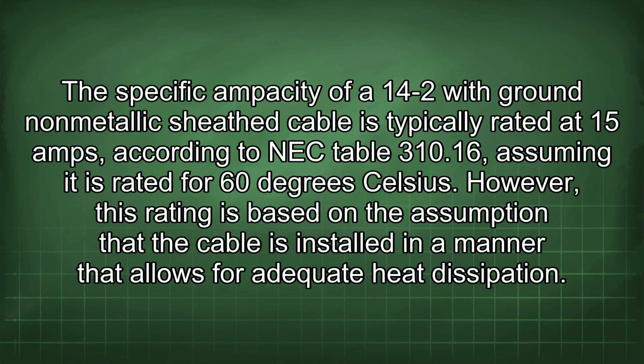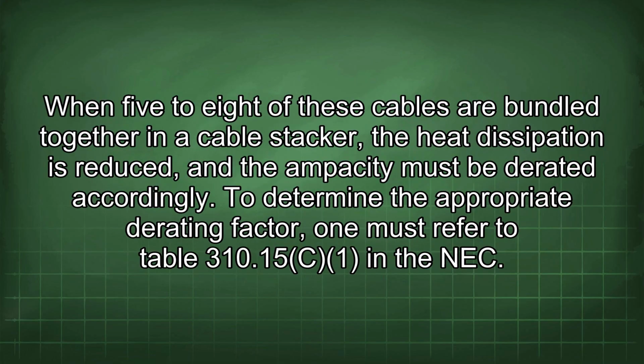The specific ampacity of a 14-2 with ground non-metallic sheathed cable is typically rated at 15 amps, according to NEC Table 310.16, assuming it is rated for 60 degrees Celsius. However, this rating is based on the assumption that the cable is installed in a manner that allows for adequate heat dissipation. When 5 to 8 of these cables are bundled together in a cable stacker, the heat dissipation is reduced and the ampacity must be derated accordingly.